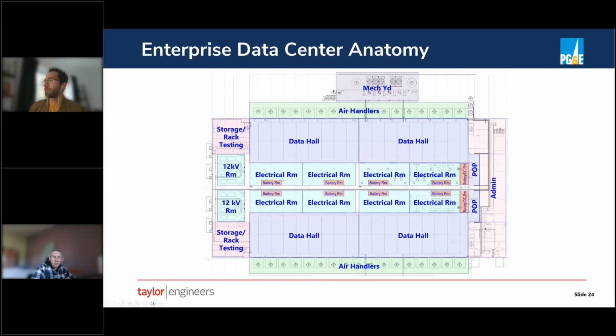On the electrical side, you see that there are 2 electrical rooms feeding each of the data halls, and these ultimately have power that emanates out into the data halls, in this case by something called a Starline busway, sort of an overhead form of electrical distribution to which you can plug in bus plugs that then serve the downstream servers.